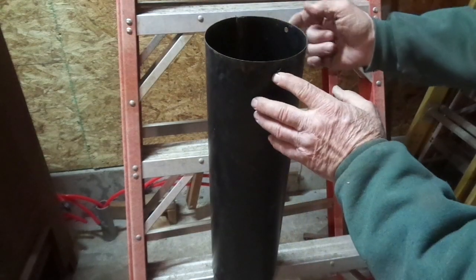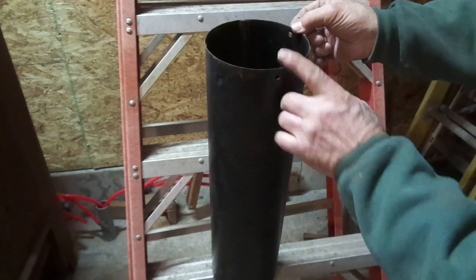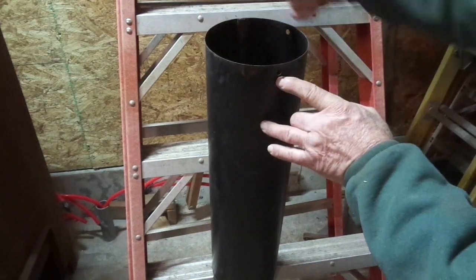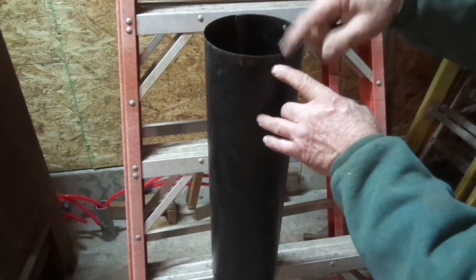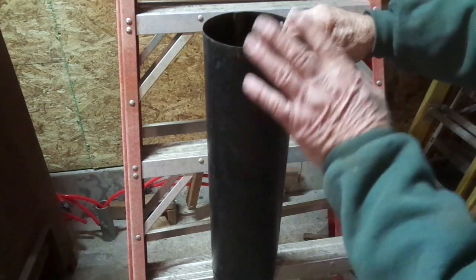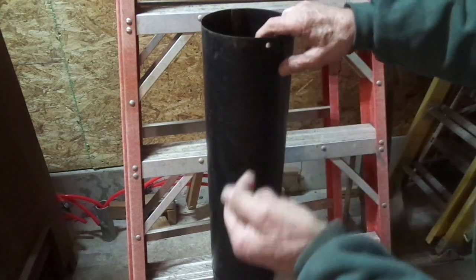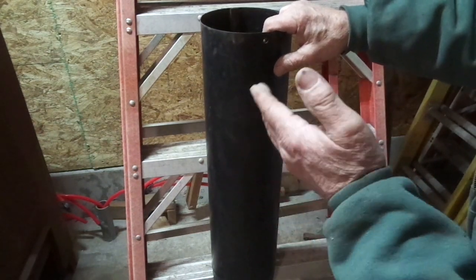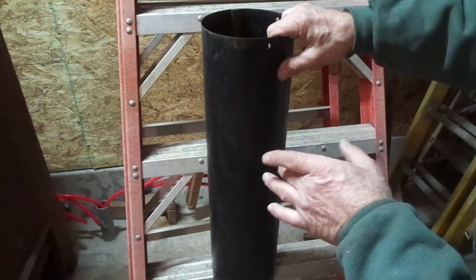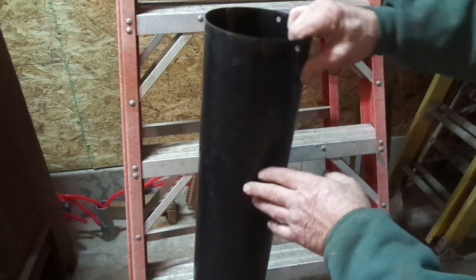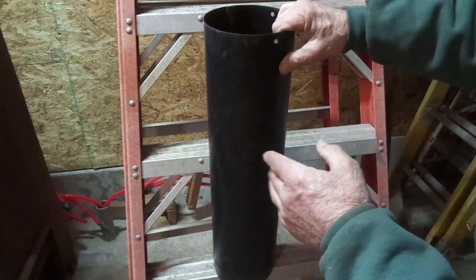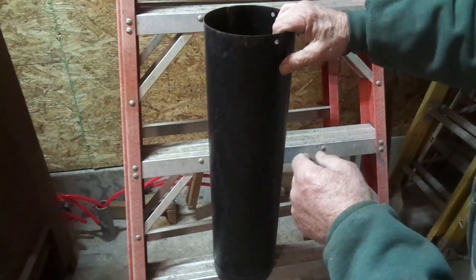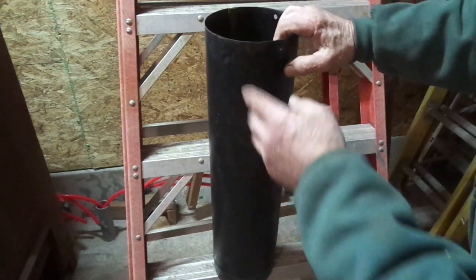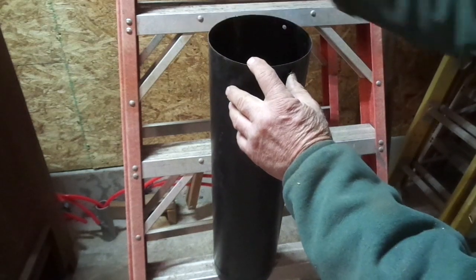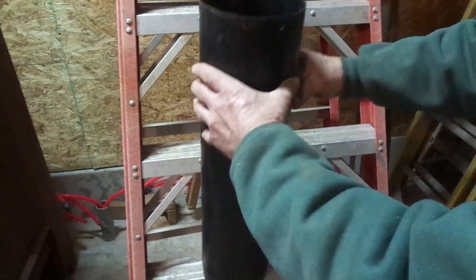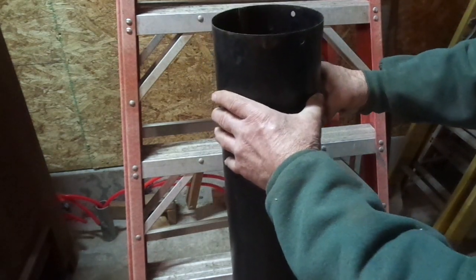Put 3 screws in every flue pipe. Here's one here, and one here. Try to get your 3 screws approximately 120 degrees apart. In the event of a volatile flue fire, you cannot believe what happens to these flue pipes. They'll move back and forth. The volatility of them is just beyond understanding unless you've experienced one. And with the triangulation of 3 different screws, the flue pipe itself will remain rigid.